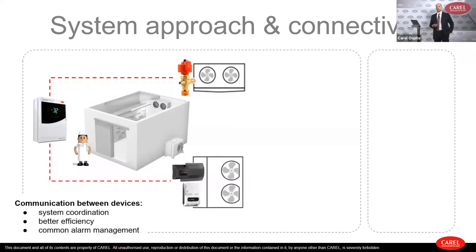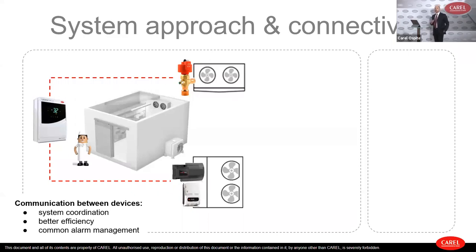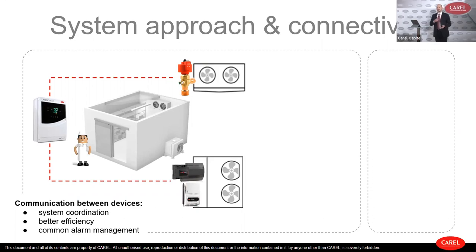Can we do more? If we connect a smart condensing unit — for example, a variable speed condensing unit — it can speak together with the control panel and the electronic expansion valve. This is a coordinated system because information is exchanged by all three parts. We can have better efficiency and common alarm management. If something happens on one device, the other devices can take an alternative path to manage the emergency.